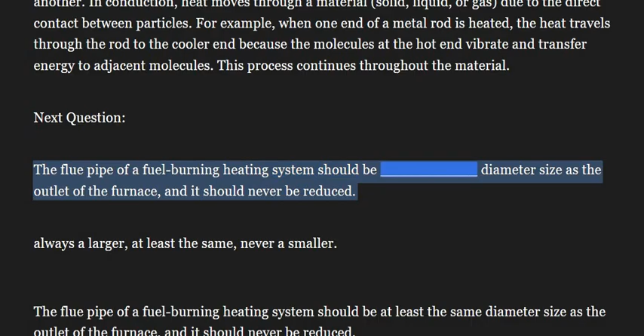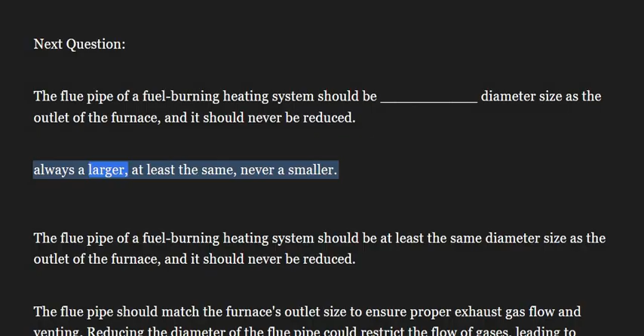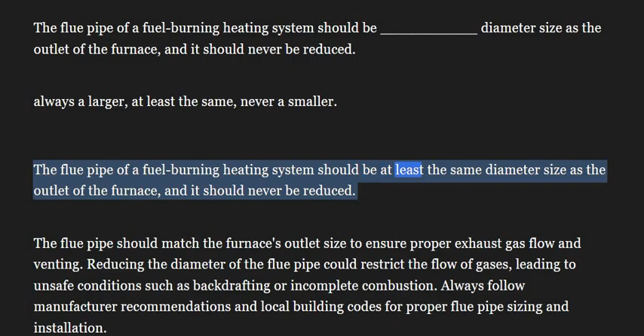Next question. The flue pipe of a fuel-burning heating system should be diameter size as the outlet of the furnace, and it should never be reduced. Always a larger, at least the same, never a smaller. The flue pipe of a fuel-burning heating system should be at least the same diameter size as the outlet of the furnace, and it should never be reduced.